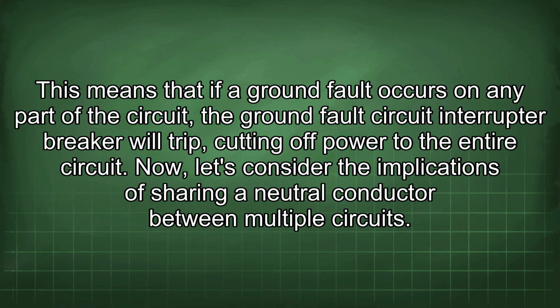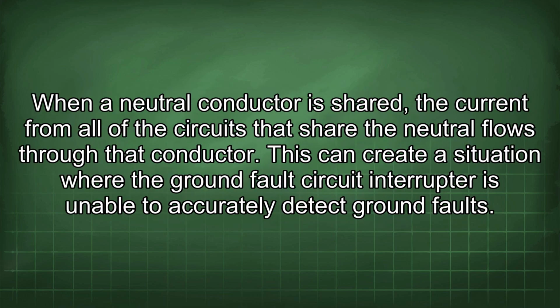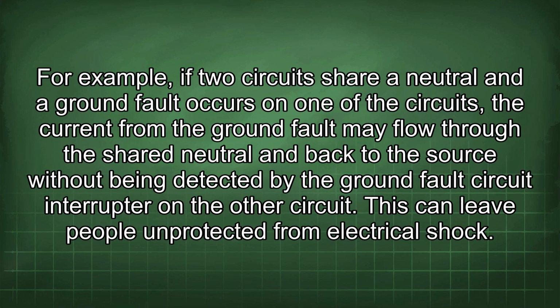Now let's consider the implications of sharing a neutral conductor between multiple circuits. When a neutral conductor is shared, the current from all of the circuits that share the neutral flows through the conductor. This can create a situation where the ground fault circuit interrupter is unable to accurately detect ground faults. For example, if two circuits share a neutral and a ground fault occurs on one of the circuits, the current from the ground fault may flow through the shared neutral and back to the source without being detected by the ground fault circuit interrupter on the other circuit. This can leave people unprotected from electrical shock.